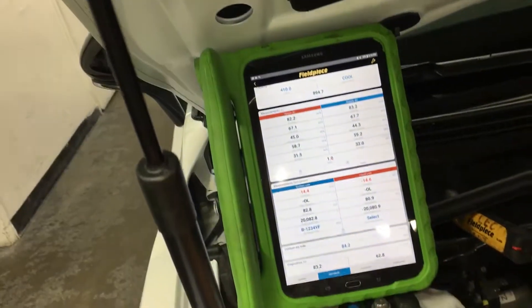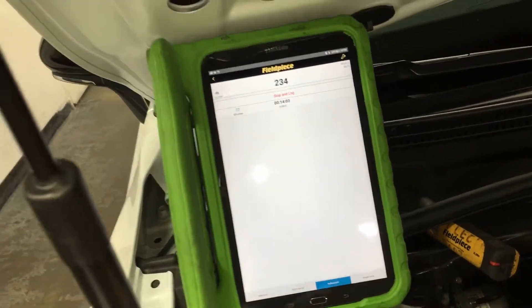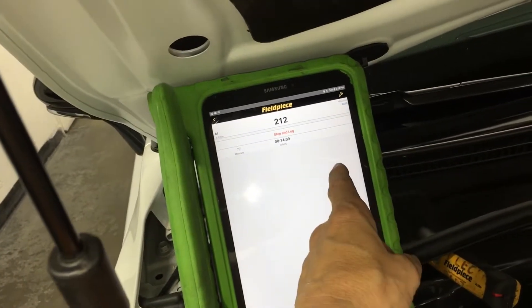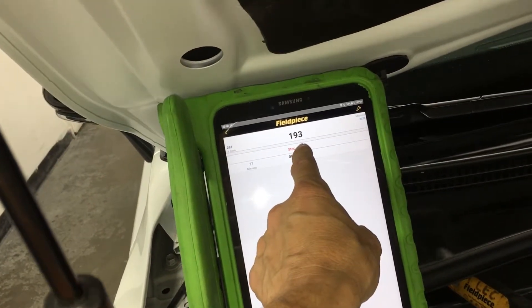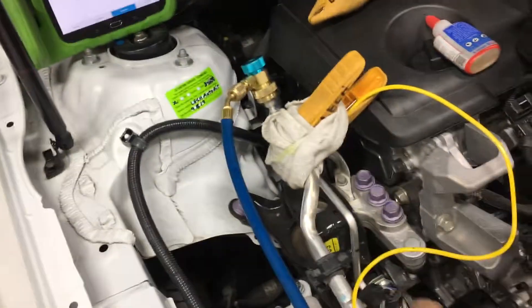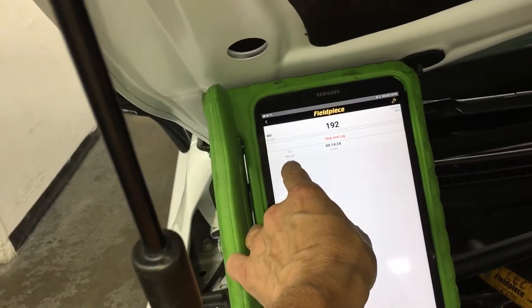One thing about the Fieldpiece I haven't shown you yet — you can actually do your evacuation monitoring through here, and it'll log it over time. Here we show we're at 245 microns. I have gotten as low as 77 microns before I hooked it up to the system — that was telling me my gauges were clean and dry at that time when I started.